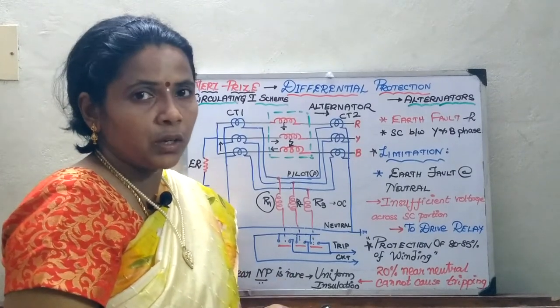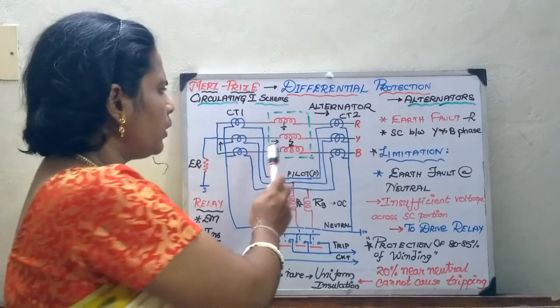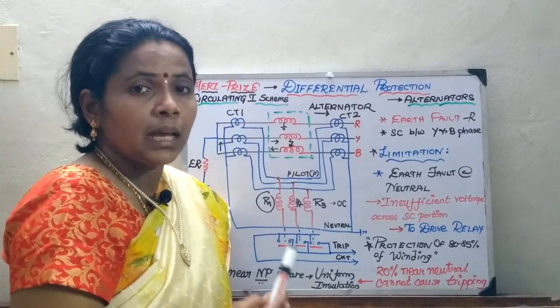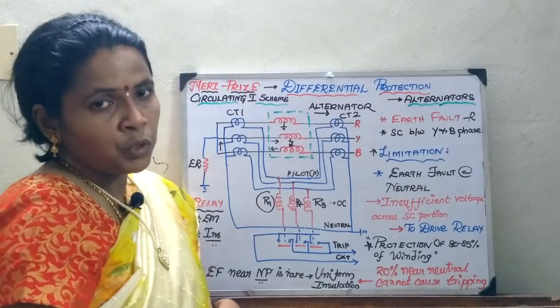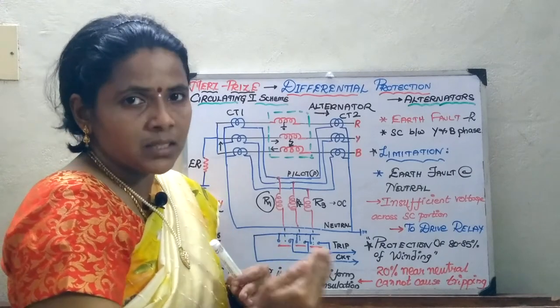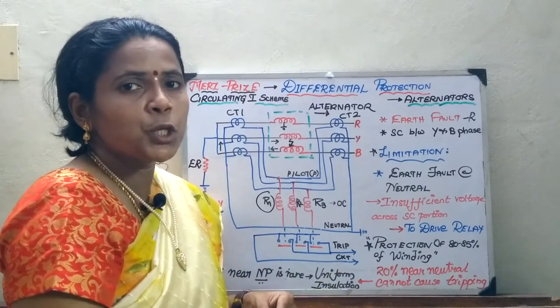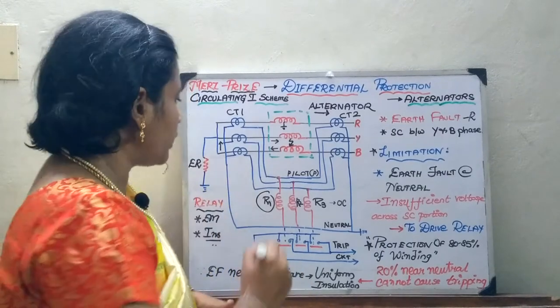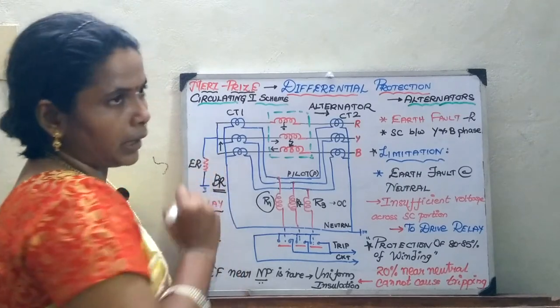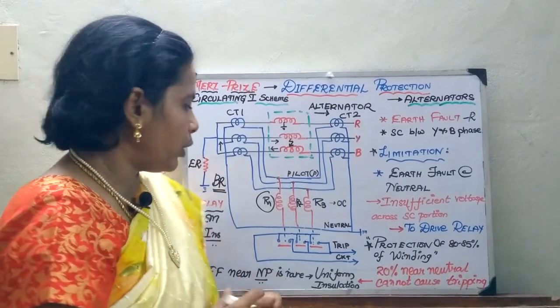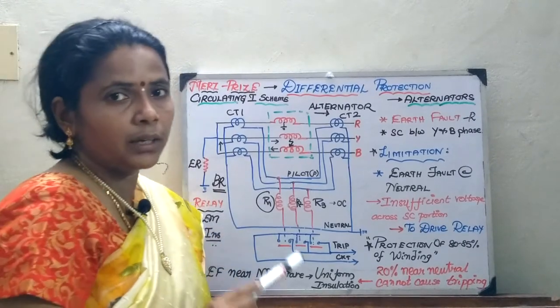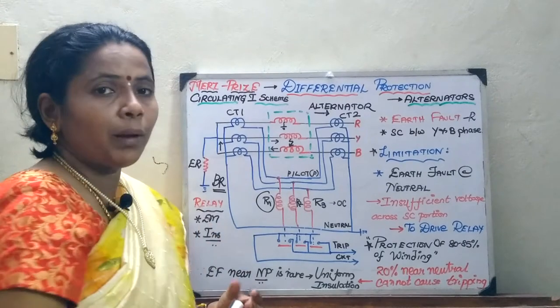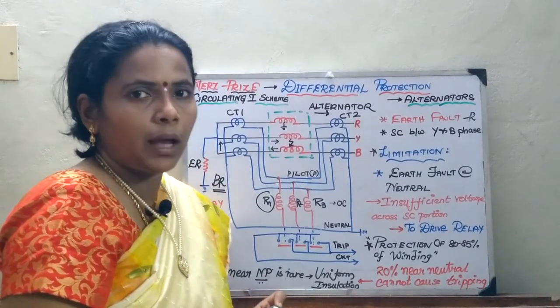In practice, the CT is placed near the alternator while the other CT is near the switchyard, so the pilot cable length can vary. If the pilot distance varies, the differential relay may operate under normal conditions — which must be prevented. To manage this, balancing resistors are connected as required. The relay used is an electromagnetic instantaneous type, since the alternator is a critical power system component and must be tripped immediately on fault.